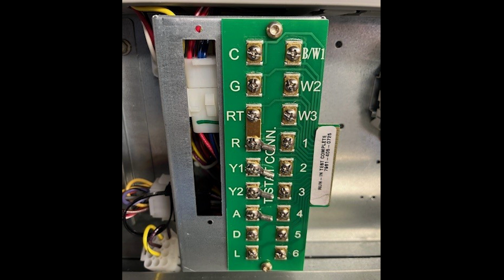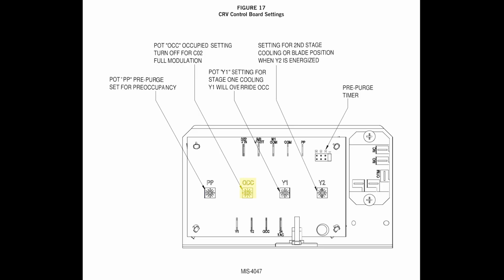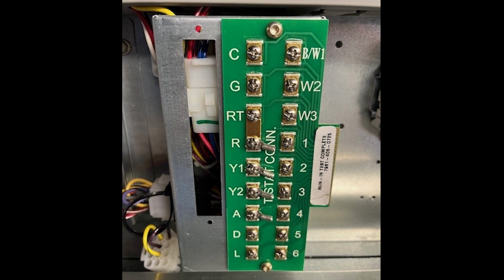With power to the unit, jumper wire R to A on the low voltage terminal block. The blower will energize on low CFM mode. Turn the OCC pot clockwise to open the damper. When set, remove the jumper wire from R to A to test and demonstrate the damper spring load closes and the indoor motor stops.